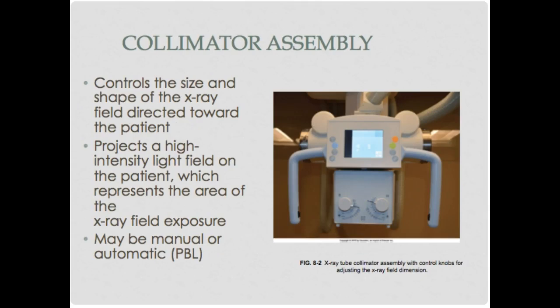The collimator assembly controls the size and shape of the x-ray field directed toward the patient. It projects a high-intensity light field on the patient representing the area of the field. When you adjust your collimator, it has a light, a mirror, and lead shutters. The lead shutters block the light just as they do with x-rays. Wherever your light is represented is where your x-ray field should be, though some may be off slightly — you need to know how much and which direction to avoid clipping pertinent anatomy.